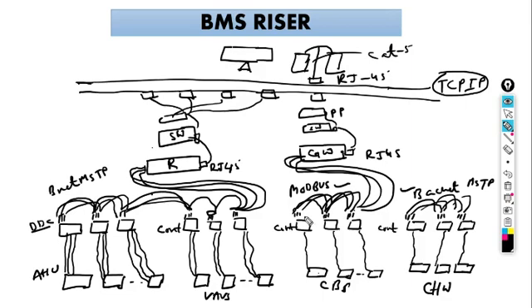You just need to understand these cables. The cables connected from the equipment, from the sensors to the controllers, are hardwired cables, already inside the sensors. From DDC to DDC it is a 3-wire cable, a daisy chain, 3-wire cables. They can have other specifications, like 16 AWG, and for this, 24 AWG American Wire Gauge.